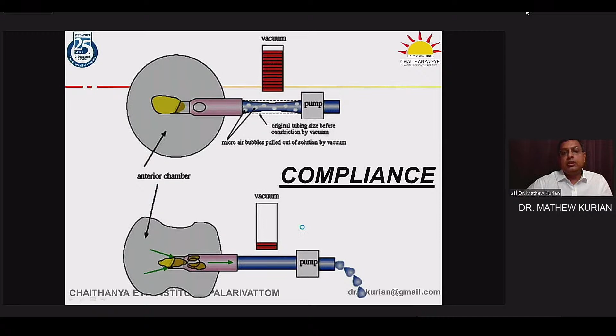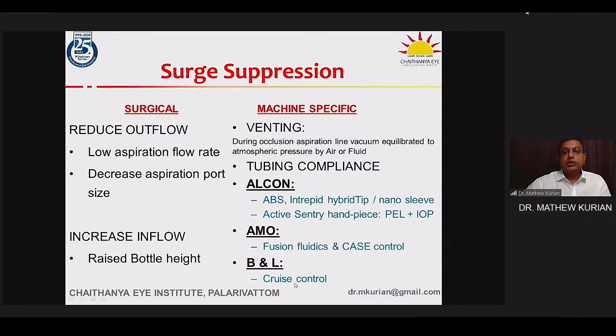Machine-specific venting, which is now by fluid mostly, is present almost in every machine. Most of the machines you will get low compliant tubings, so that is not a very major feature anymore. There are some things which are specific to machines. Alcon has got the ABS. I will go into it in a little detail now. The tips and the sleeves. Active Sentry is something where the handpiece is modified and sensors are present in the handpiece to maintain the IOP better, and having the sensor in the handpiece ensures that the machine is always working at the patient's eye level. AMO or Johnson & Johnson now has got the Fusion fluidics and the CASE control. Bausch & Lomb has got Cruise Control.